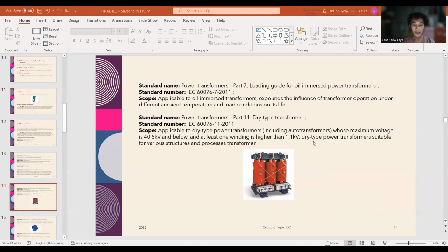And also, this part of the parameter standard gives mathematical models for judging the consequence of different loadings with different temperatures of cooling medium and with transient or cyclical variations with time. So these models provide for the calculation of operating temperature in the transformer, particularly the temperature of the hottest part of the windings. This hot spot temperature is in turn used for evaluation of the relative rate of thermal aging and the percentage of life consumed in a particular time period. So the modeling refers to small transformers, here called distribution transformers, and power transformers.